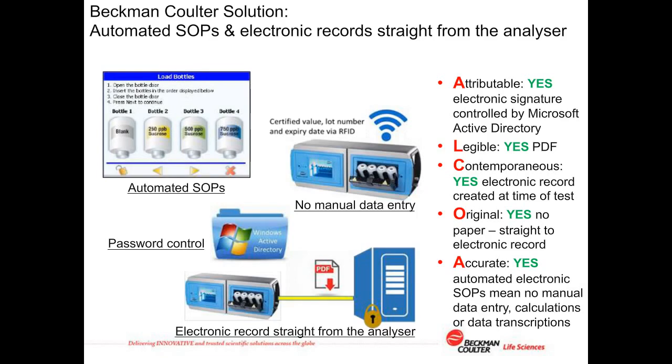Of course, with a modern Ethernet network system, those sorts of gaps are quite unusual and typically temporary. And the data, the PDF, is sent using TCP/IP, which is a very resilient network protocol anyway. But yes, it holds the data, and it waits until there's been a successful export, and then it sends it out actually using file transfer protocol, FTP. So there's a handshake involved with the remote server. So until it receives that handshake, it will not delete the file.